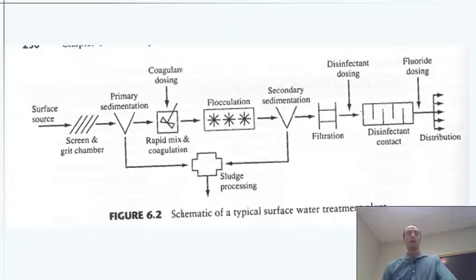And so we have pretty clean water, but we've not necessarily taken care of any of the viruses, and there's probably a good potential for bacteria also to be floating around. So here's where we would add a disinfectant, and you see it's drawn as a plug flow reactor. That is quite typical for disinfection processes, and if you stop and think about that, we'll come back to that concept, but that makes a lot of sense when we want a high percentage removal. So we want 99.9% or whatever as sort of the safety to make sure that there's no more bacteria or viruses there at infectious levels.